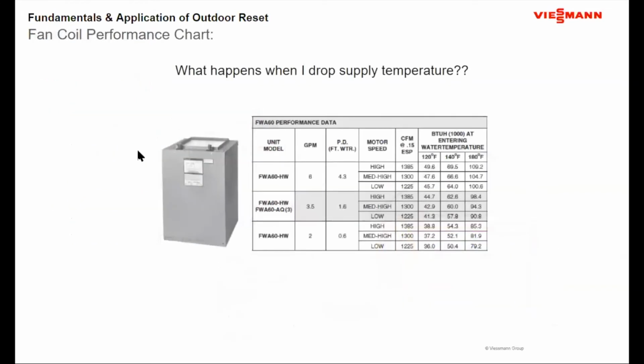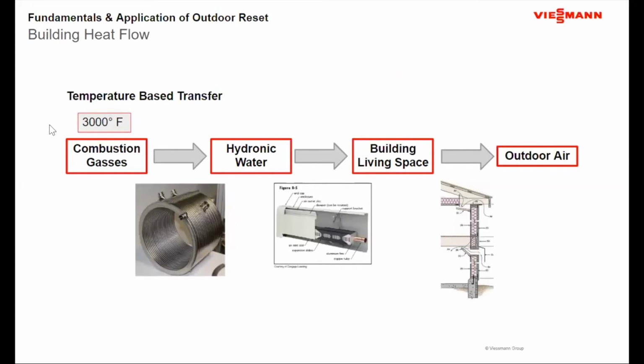Same thing when I do air handling units. So if I look at 3.5 gallons here, and I look at the 180 degrees, 140 degrees, 120 degrees, you'll find a little bit of a bigger jump from here to here on the spacing. But if you look at the output of this heat emitter, it's pretty linear through this range from 180 to 120. So for a corresponding drop in water temperature, I'll see a corresponding drop in the output of the heat emitter. So we start to look at trying to change the temperature coming out of a heat emitter to balance to the outside temperature. If I can change the water temperature, I can change the performance of that heat emitter, whether it's baseboard, air handling units, or radiant. Okay, so we start to do outdoor reset.